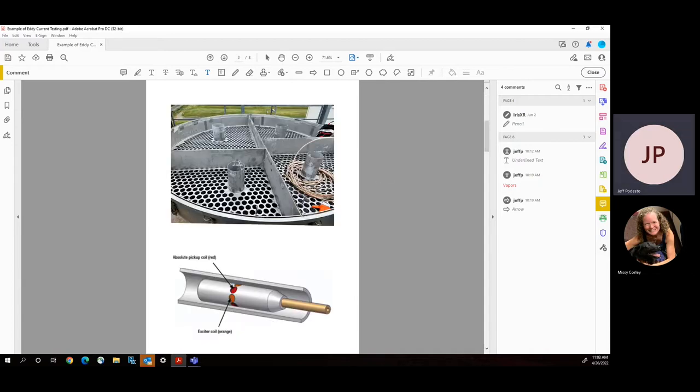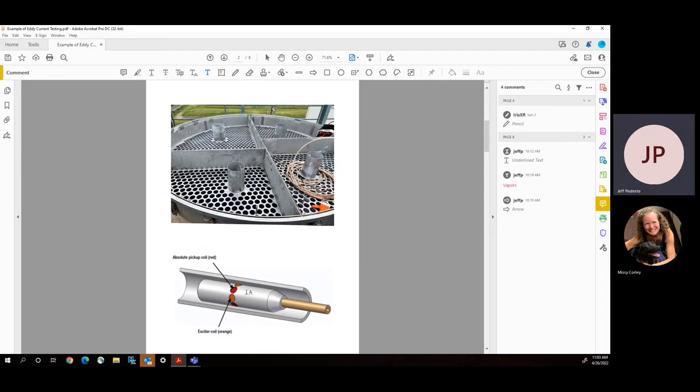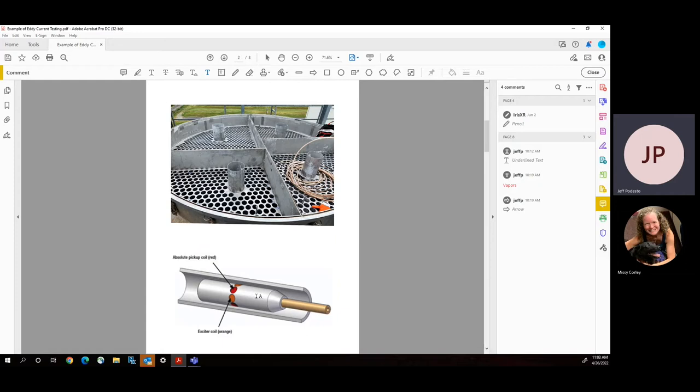So, typically what is required is that you would need to clean your evaporator and remove the top of the evaporator. As you can see in one of these pictures, there's a coil of wire here, which is attached to a probe, and then that probe is dropped down the length of each one of the tubes. And that information that comes back is delivered into a computer, and there is a software package that goes along with the probe that analyzes what is happening in the tube.